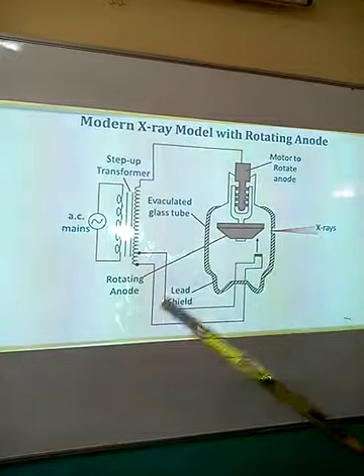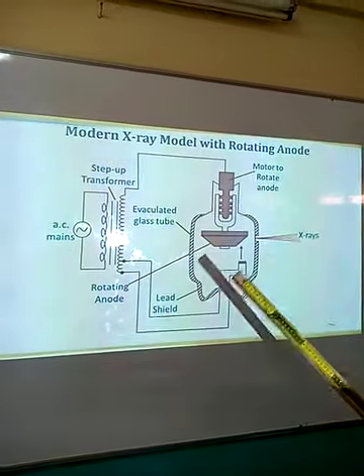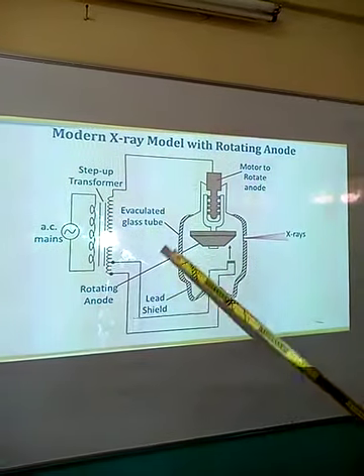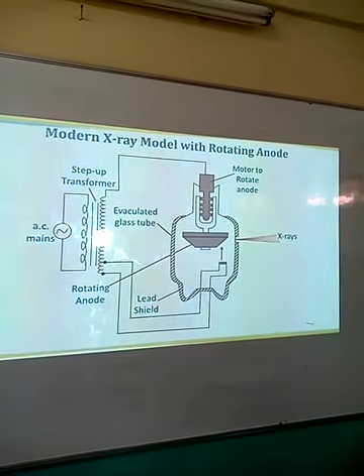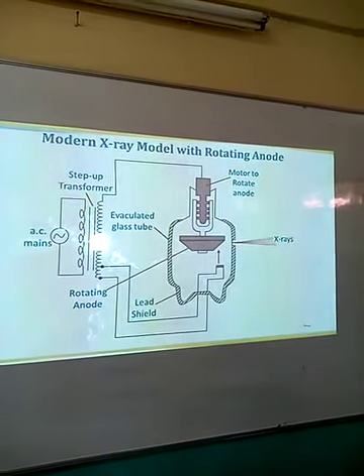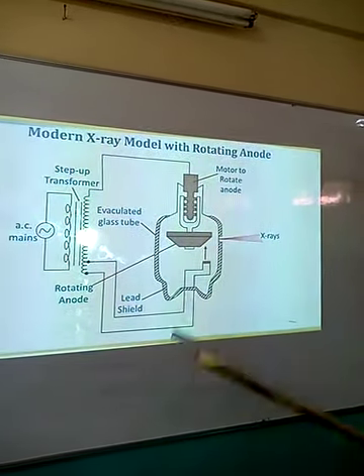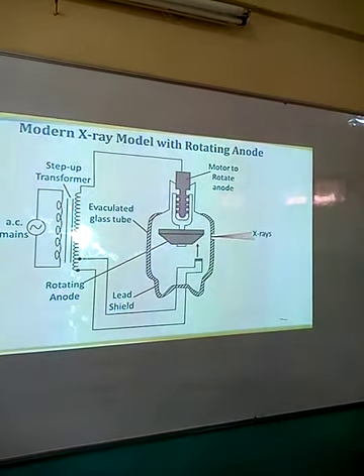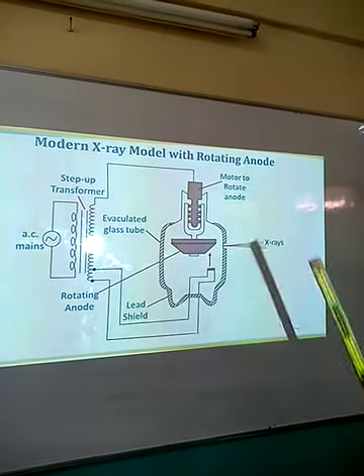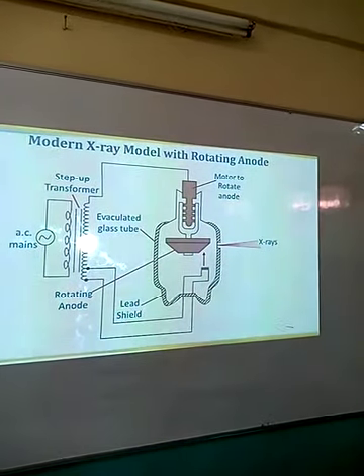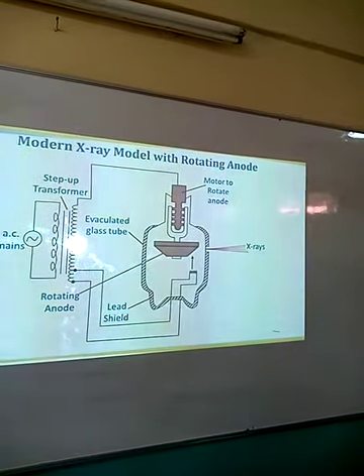As you can see, the anode is attached to the motor. The voltage is stepped up to a high value in order to produce the electrons at the cathode. The tube itself is surrounded by the lead metal or lead sheet. The purpose of that is to trap any stray X-rays being produced from the tube. X-rays are very dangerous and therefore their production must be controlled. That is why there is a very small window left where X-rays can only escape to the intended target. The anode is also inclined at 45 degrees, to enable the channeling of X-rays directly to where it is intended.